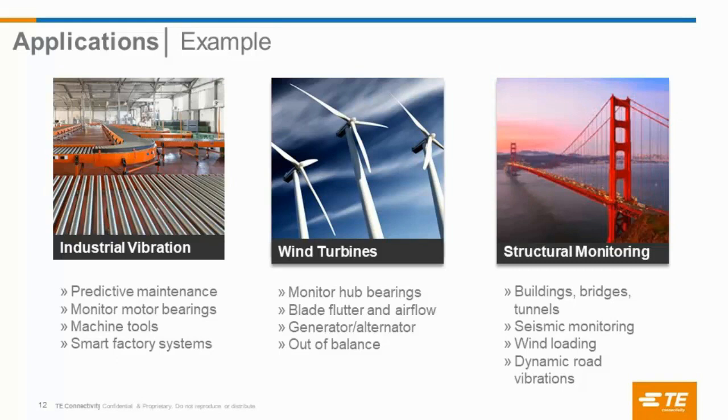You also find these accelerometers being used in electric motors and drive systems for equipment all over factories. As you might expect in a manufacturing facility, every machine's got electric motors in it, and the electric motors have bearings, and you can monitor the health of that motor simply by listening to it. They have very standard acoustic signatures that will signal a healthy motor. And as the motor starts to develop problems, those acoustic signatures change, and we can actually listen to those events with our accelerometer products.